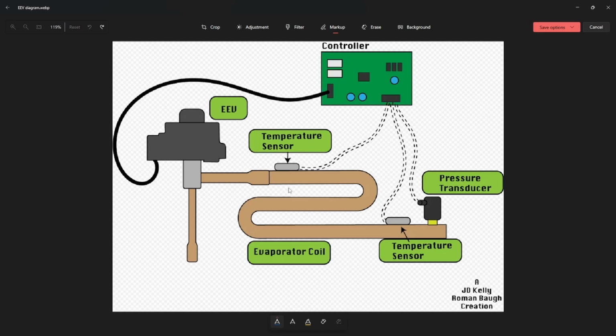Always try to put them back in the same place you got them from, and always make sure they're wrapped in insulation foam tape. Make sure they're properly secured to the pipes. Treat them just like a sensing bulb for a TXV, because essentially that's what they're doing. They're acting as the sensing bulb for the TXV, just using thermistors and electrical signals instead of us relying on a mechanical connection. Now, the second most frequent issue you'll find is going to be the stepper motor.